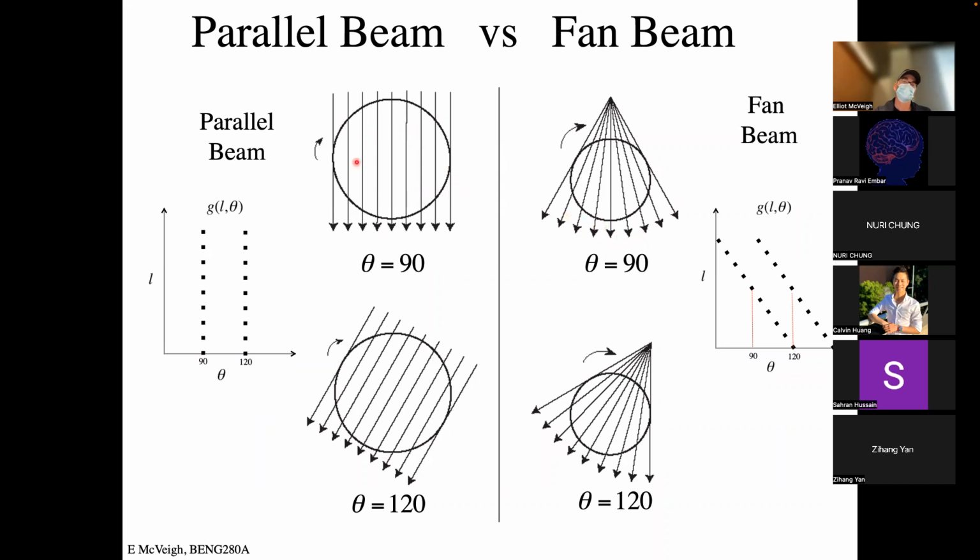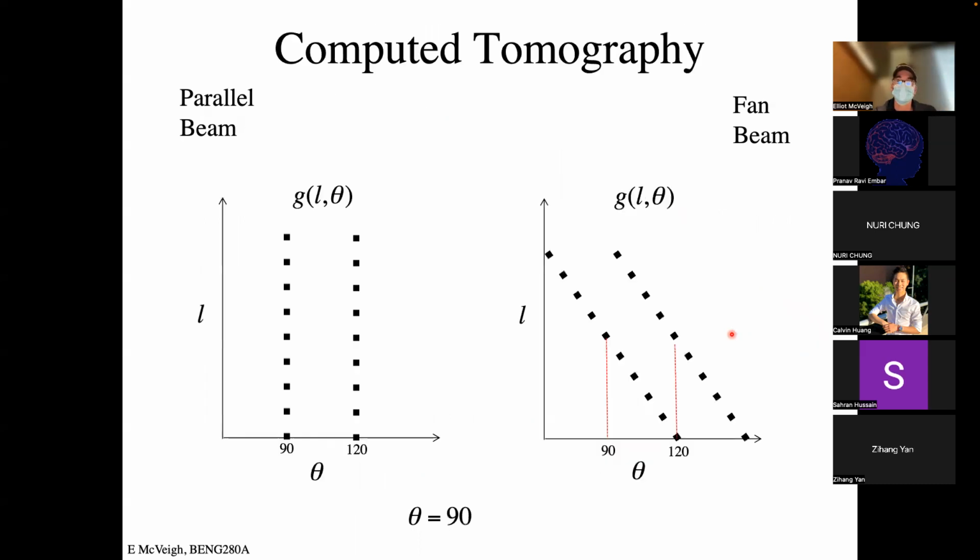When you reconstruct the parallel beams by sampling through this space, the interesting thing is that the parallel beam, at one specific L value, actually gets sampled at a different time than at another L value, right? At that same angle. And so there's a distribution of times for each one of those views. And so it makes the data slightly more complex if it's changing in time.